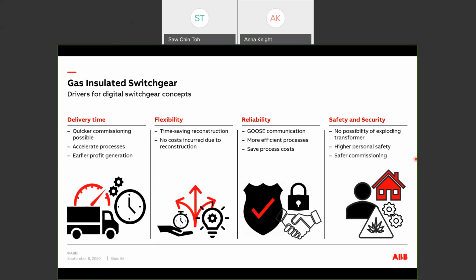The Rogowski coil current and voltage sensors in combination with modern ABB relays and IEC 61850 communication plus GOOSE messaging provide a lot of flexibility to the customer. If changes are required late in the project, it can be done by just reconfiguring the relay and its logic.